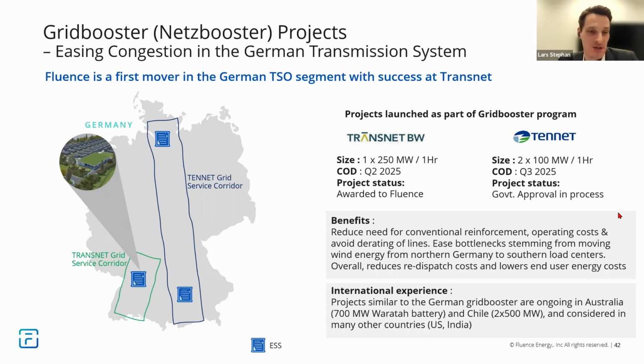So grids, especially in Germany, but in many other countries around the world, are typically operated on an N-1 contingency requirement. That means we always keep spare capacity in our transmission grid in case we have a contingency event, like a fault at the substation, or a problem with a line. One line goes out, we cannot use it anymore. The other lines that we have in a grid area can pick up the electricity flows that were previously on the line that now had a fault condition. So this means, in turn, that we always keep spare capacity on our lines. So we have lines which we're actually not utilizing because we're holding back capacity for security reasons.